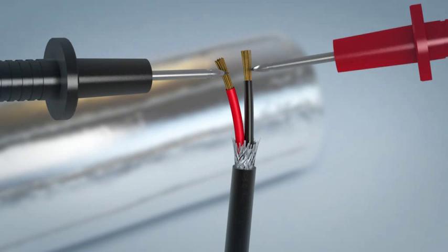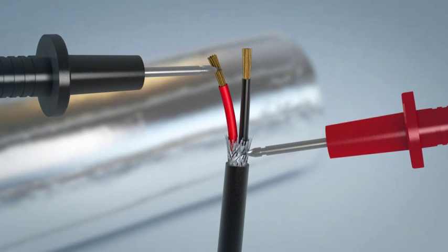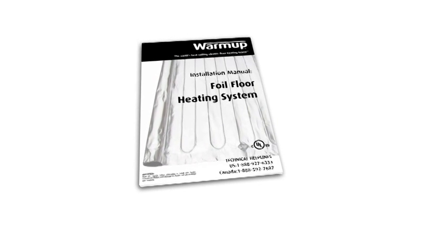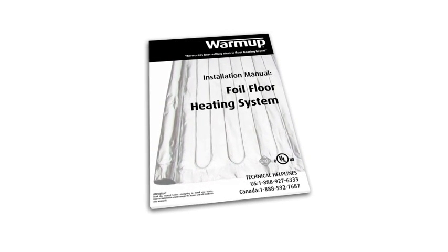Perform another multimeter test to check that the heating mat has not been damaged and make a note of your reading in the Warm-up installation manual. If your reading has changed, call Warm-up immediately. Do not continue working.